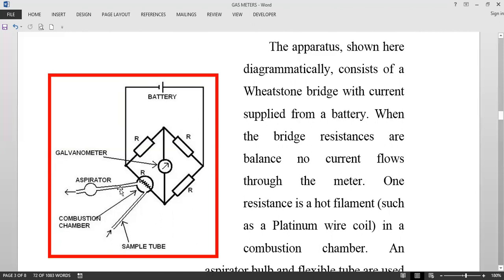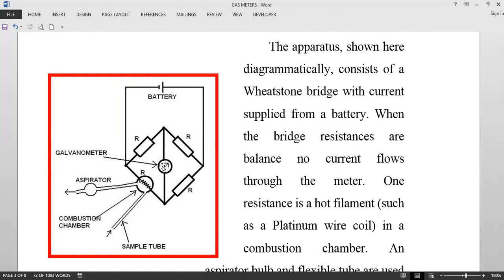There is an aspirator bulb. When you switch on this equipment and press this aspirator bulb, a sample of the gas mixture from the space is withdrawn into it. It comes into this resistance and then it burns on the filament. When it burns, this resistance changes and the Wheatstone bridge is no longer balanced. Due to this burning, the resistance change is deflected as a current on the galvanometer, which shows the reading of the gas inside.